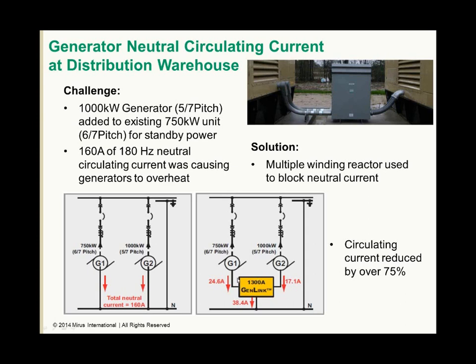The residual amount of current here is very likely predominantly due to single-phase, phase-to-neutral loads, because those will still want to draw the current, and the GenLink allows those currents to flow. So a substantial reduction in the overall neutral current, offloading the generators, causing them to run much cooler than with the circulating currents.